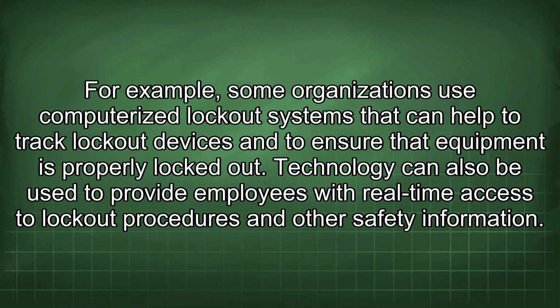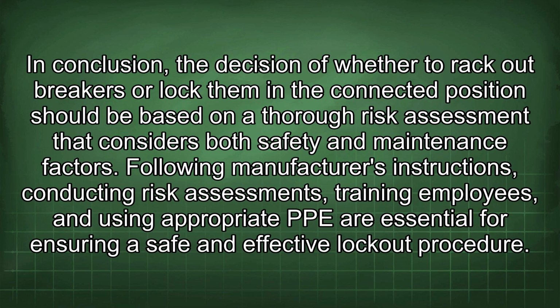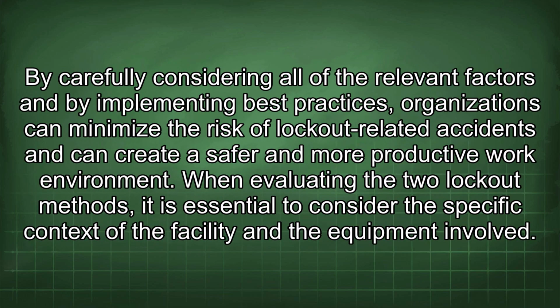For example, some organizations use computerized lockout systems that can help to track lockout devices and to ensure that equipment is properly locked out. Technology can also be used to provide employees with real-time access to lockout procedures and other safety information. In conclusion, the decision of whether to rack out breakers or lock them in the connected position should be based on a thorough risk assessment that considers both safety and maintenance factors. Following manufacturers' instructions, conducting risk assessments, training employees, and using appropriate PPE are essential for ensuring a safe and effective lockout procedure. By carefully considering all of the relevant factors and by implementing best practices, organizations can minimize the risk of lockout-related accidents and can create a safer and more productive work environment.